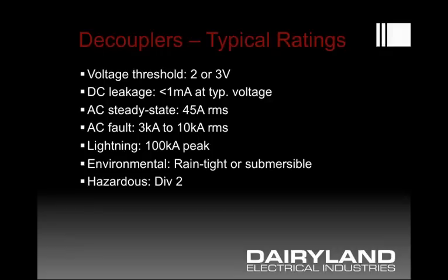The typical ratings for such a device would be that it only needs to block DC current flow up to a threshold of two or three volts, because pipeline operators would not normally have a CP voltage any higher than that, and one wouldn't want a threshold so high as to be unsafe. At the same time, the DC leakage current through the device should be extremely low — ideally zero, and it almost is for the typical solid state device. It's well less than a milliamp at any typical voltage, or even at the threshold, not more than several milliamps.